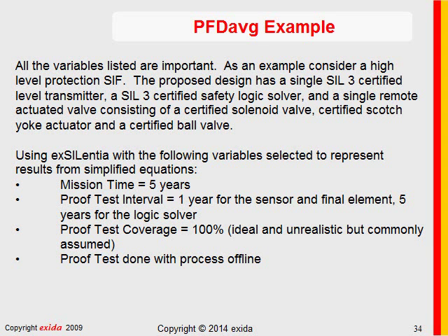If a transmitter and sensor is pulled out, overhauled, calibrated, and put back in place once a year, should this be considered a mission time or a proof test? A transmitter and the sensing device, like a remote seal, or in the case of a temperature transmitter, the thermocouple and the well. Overhauled, rebuilt. I assume you either put in new components or completely restore the old components.